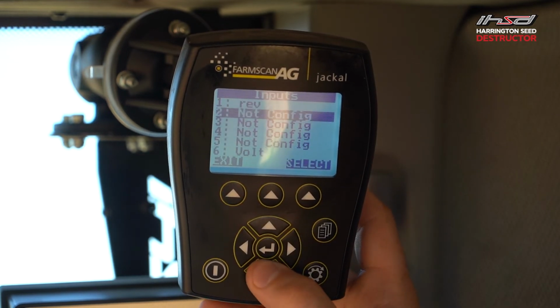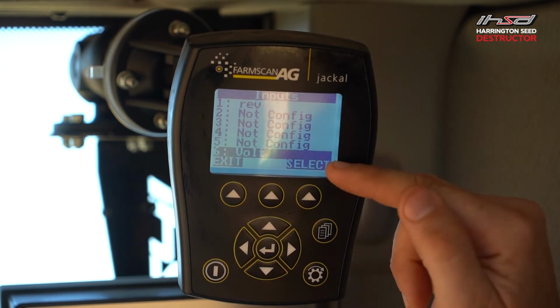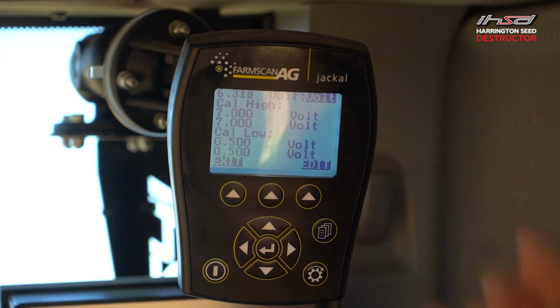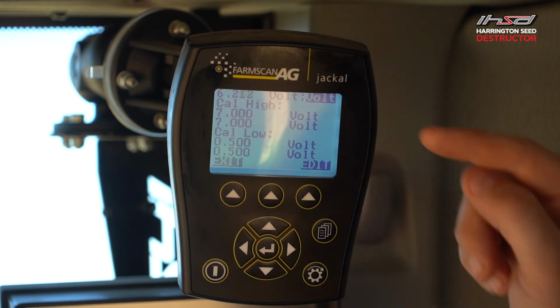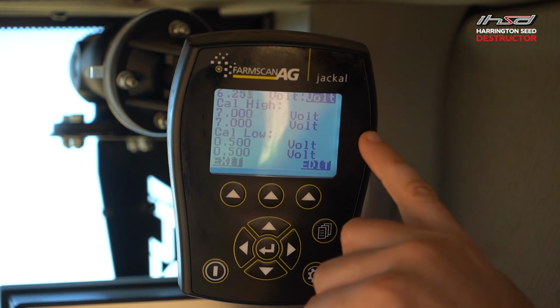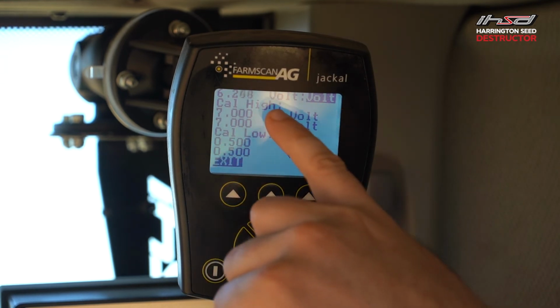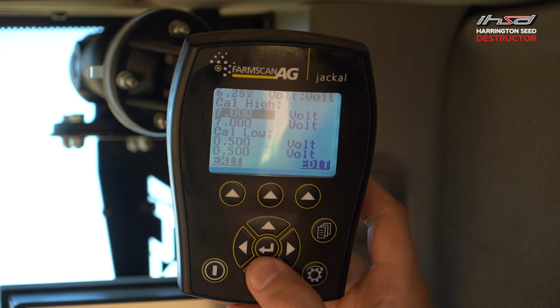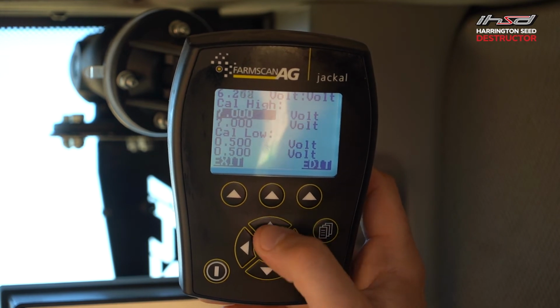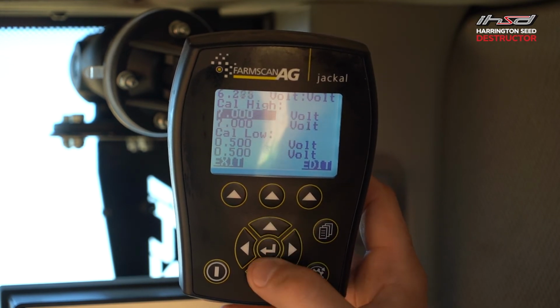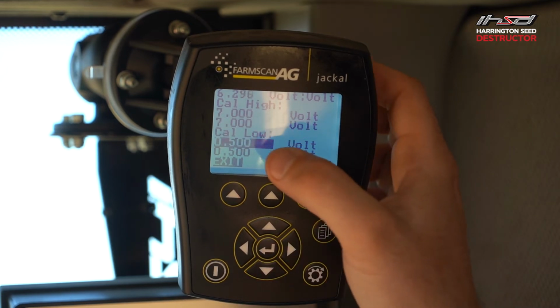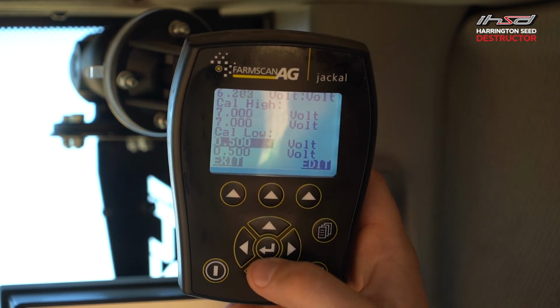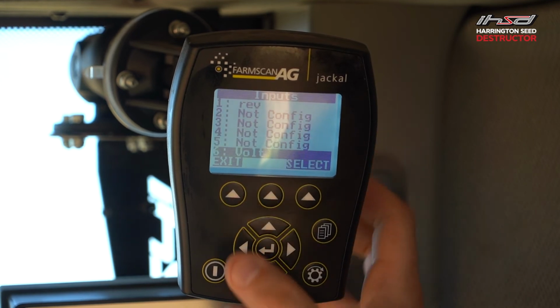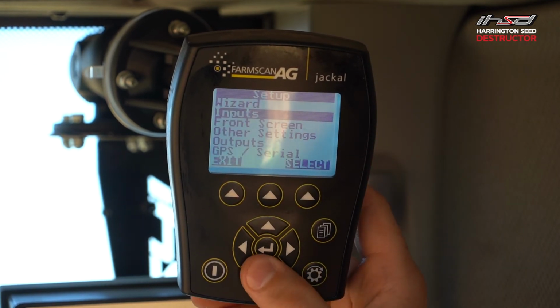This is a common mistake made when setting up the Jackal. Moving on to the vibration sensor, we go down to input number 6. Press enter. Again, a common mistake with how the Jackals are set up. This needs to be on volt. Then both calibration high values need to be 7. Both calibration low values need to be on 0.5. Moving on to the front screen.